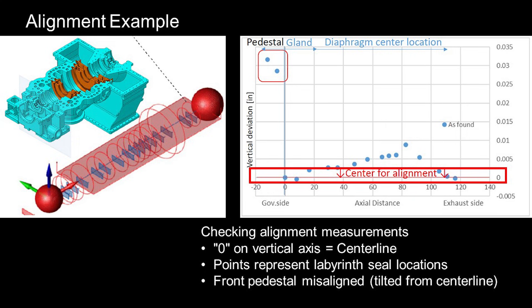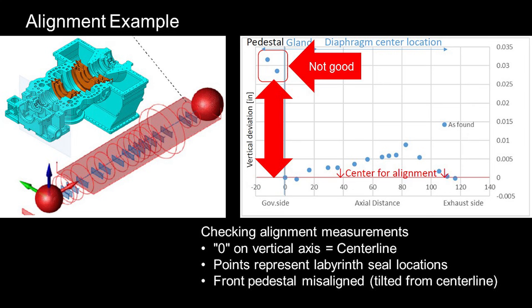Here is an example of how to check alignment data. The vertical axis, zero, represents the alignment centerline, and each dot represents the measured locations. This graph highlights that the front pedestal is tilted, with data points significantly off from the centerline.